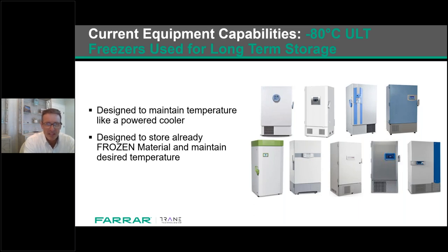Great. Thank you, Steve. On this slide, I feel confident saying most of you have or are currently using cold wall minus 80 degrees C freezers, such as the one depicted on this slide. Again, they're meant for long-term storage. The cold wall freezers range, as you know, from 18 to 33 cubic foot, which I believe would be 600 liter to roughly 900 liter, reaching for storage of small samples, just like Steve mentioned. But they could also accommodate a few large containers of frozen material. However, the challenge is that the overall internal temperature uniformity on cold wall, because there's no circulation of air, could vary greatly. We're talking from plus 9 to plus 14 degrees C from a temperature mapping. And the temperature recovery from door opening is also challenging because it takes slightly longer. We'll go over that in just a few minutes. Next slide, please.